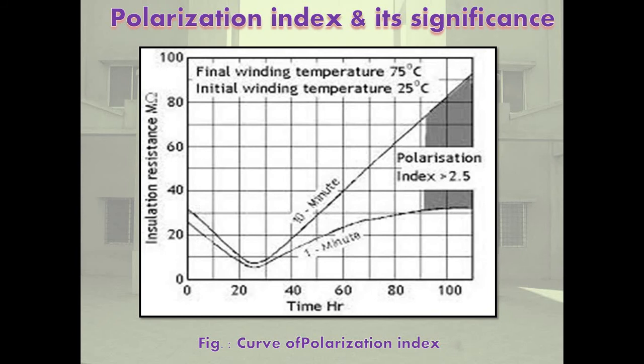While LV and ground measurement is 2.5 at 30 degrees Celsius and 1.5 at 50 degrees Celsius. LV and HV between measurement is 2.5 at 30 degrees and 1.67 at 50 degrees Celsius. Now, insulation resistance at 50 degrees Celsius is less than insulation resistance at 30 degrees Celsius. IR15 refers to the 15 second reading of the megger, and IR60 refers to the 60 second reading of the transformer megger.